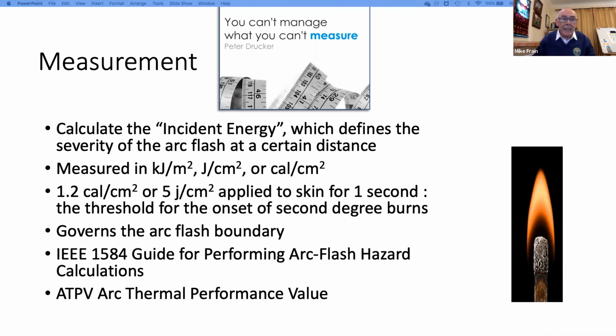IEEE 1584 is the guide for performing arc flash hazard calculations, and it's probably the most comprehensive means to determine incident energy. And it's internationally recognised, and it's also an auditable standard. So that tends to be the most popular. I'll show you one or two other ways of actually getting to an incident energy level and determining PPE and so on later.